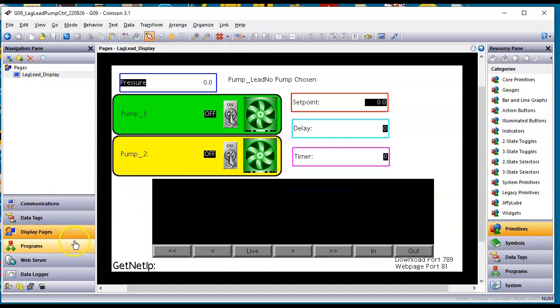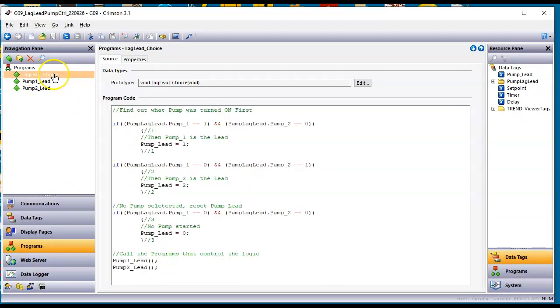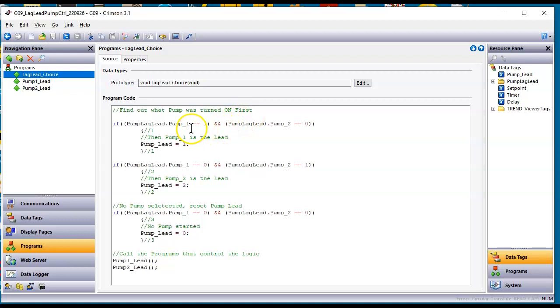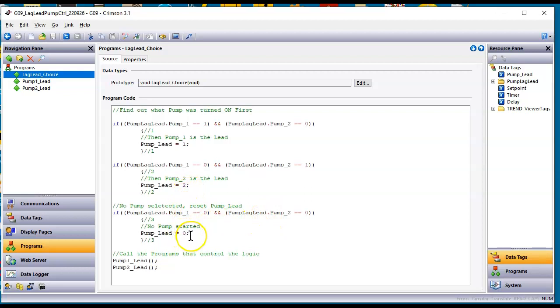Let's go look at the code though. That's where the real excitement happens. So over here I've got some code and the first thing I'm doing here is I have a program called lag lead choice. Find out what pump was turned on first. So I'm asking the question here. I'm assuming that both pumps are off from the get-go. That's the first thing here from when we start. So I'm asking here if pump one is turned on and pump two is turned off, zero and one, then obviously pump lead equals one. I have an integer tag over here called pump lead. And then the other situation is okay well if pump one is zero and pump two goes on then I'm in the pump two lead format. And then down here if neither are on then there's no pump started so pump lead equals zero.